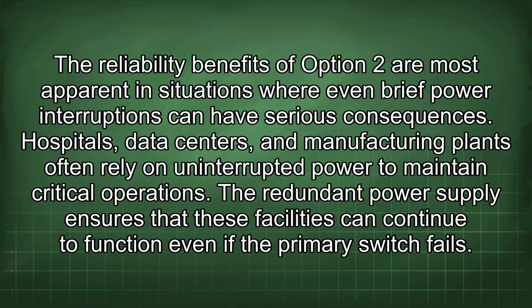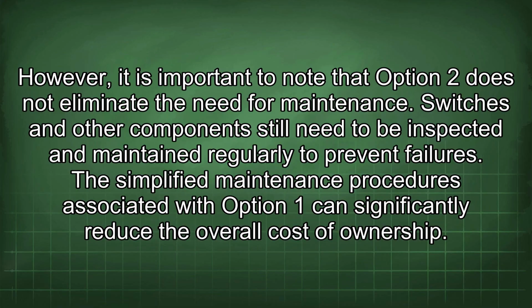The reliability benefits of option 2 are most apparent in situations where even brief power interruptions can have serious consequences. Hospitals, data centers, and manufacturing plants often rely on uninterrupted power to maintain critical operations. The redundant power supply ensures that these facilities can continue to function even if the primary switch fails. However, it is important to note that option 2 does not eliminate the need for maintenance. Switches and other components still need to be inspected and maintained regularly to prevent failures.